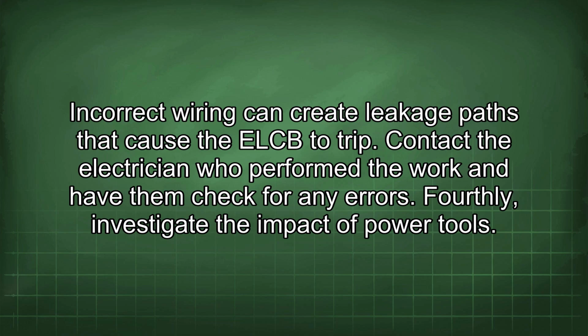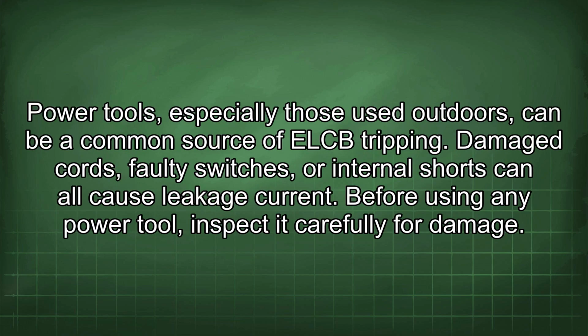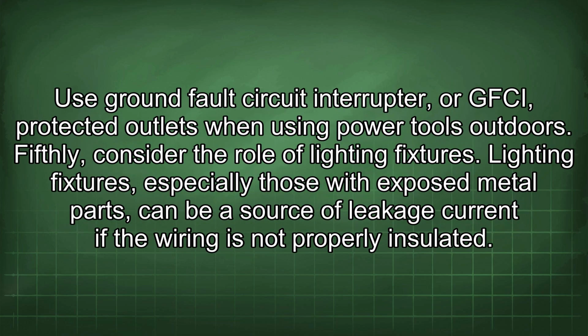Fourthly, investigate the impact of power tools. Power tools, especially those used outdoors, can be a common source of ELCB tripping. Damaged cords, faulty switches, or internal shorts can all cause leakage current. Before using any power tool, inspect it carefully for damage. Use ground fault circuit interrupter, or GFCI, protected outlets when using power tools outdoors.